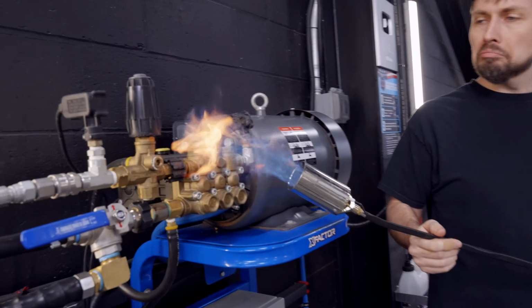There's a difference between bad seals and bad check valves. Bad seals have low pressure that runs smooth, and bad check valves have low pressure that pulsates. So let me show you what the pulsation looks like.